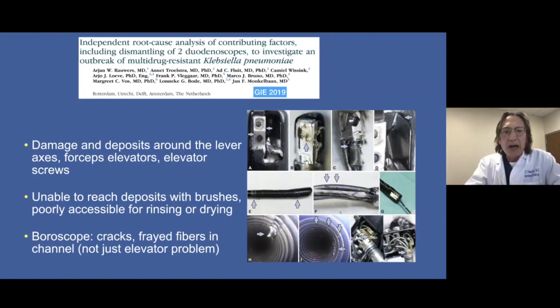So the problem here in the working channel, apart from the fact that you can't get there, right? You can pass your brushes through there, but you're doing very little, is that we're dealing with biofilm accumulation in the working channel. And this biofilm, you can see a cartoon of it here on the left side, has a complex mushroom-shaped architecture. Looks like, you know, something from deep sea diving, with these streamers. And what are formed are these water channels. And the bacteria, they attach, they are irreversibly adherent to this biofilm. And the fluid that is running through this penetrates deep within the biofilm, and it actually carries the oxygen and nutrients for the bacteria. So the bacteria love the biofilm. They flourish there. That is their home.